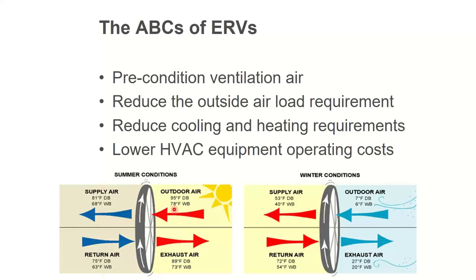On the left side is a summer scenario, works exactly the same way. But in this case, instead of me transferring heat from this exhaust stream to the outside air, I'm going to transfer heat from the outside air to the exhaust air. So I have 95 degree air coming in with a pretty nasty wet bulb of 78 wet bulb. And I'm going to send those sensible and latent BTUs on the heat exchanger to the other airstream where they will get exhausted out by this air moving through here. And then my 95 degrees gets free cooled down to 81 and my 78 gets free dehumidified down to 68. So on a 95-78 day, my evaporator coil is going to think it's 81-68 coming in.